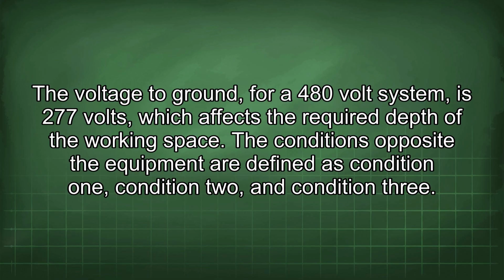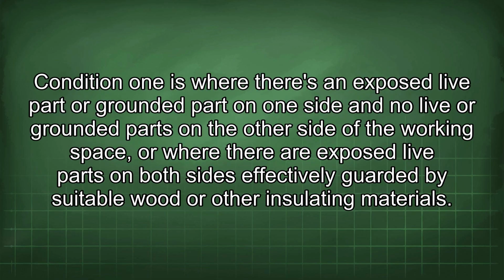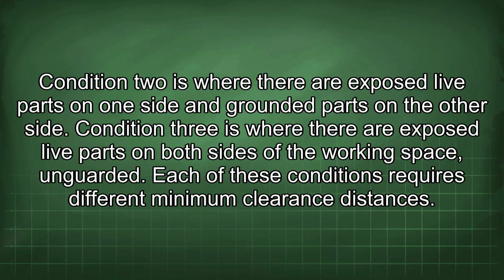The conditions opposite the equipment are defined as Condition 1, Condition 2, and Condition 3. Condition 1 is where there's an exposed live part or grounded part on one side and no live or grounded parts on the other side of the working space, or where there are exposed live parts on both sides effectively guarded by suitable wood or other insulating materials. Condition 2 is where there are exposed live parts on one side and grounded part on the other side. Condition 3 is where there are exposed live parts on both sides of the working space, unguarded. Each of these conditions requires different minimum clearance distances.